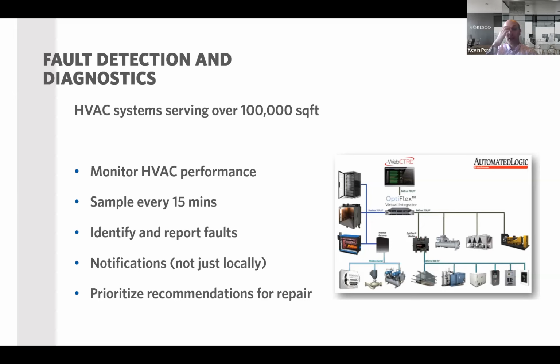They're actually saying that, a lot of times when I go into buildings and look at the building automation system, there's always this little red bell kind of chiming in the corner. And I always pull that up to see what that is. That's the alarm list. That's the notification system that something's not right.